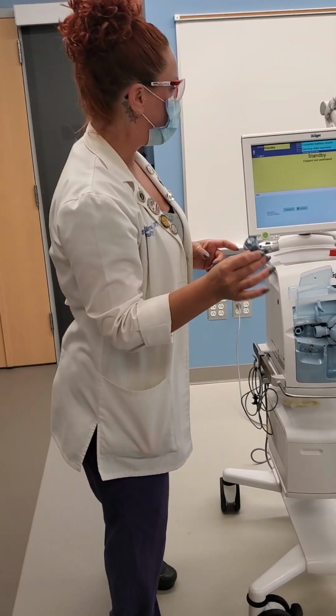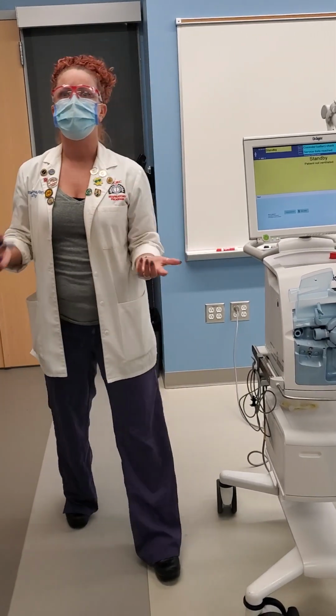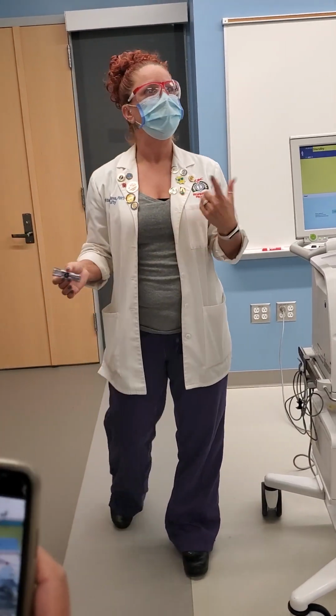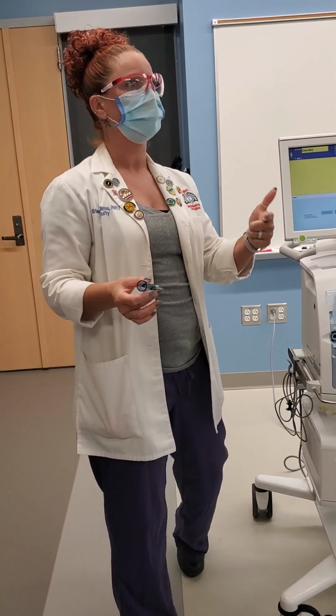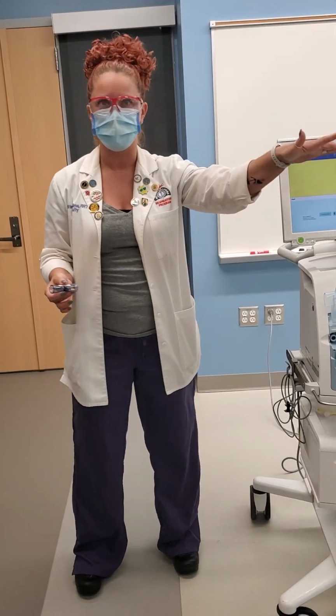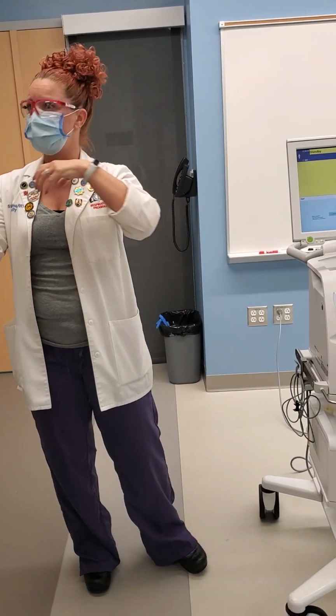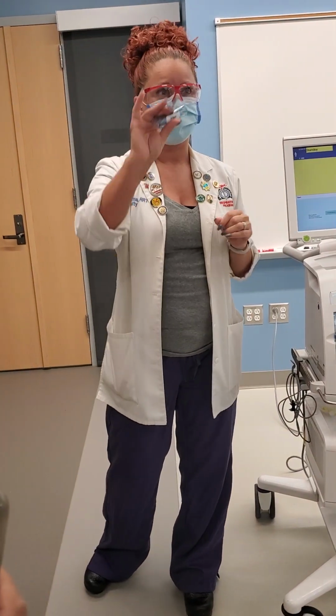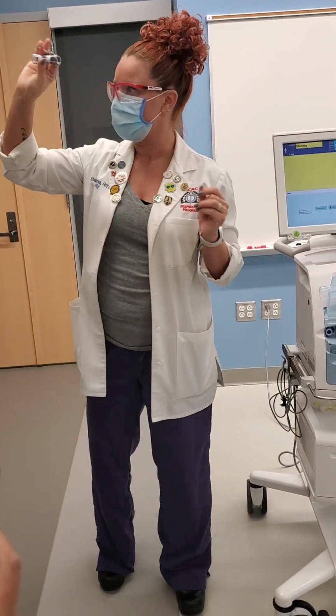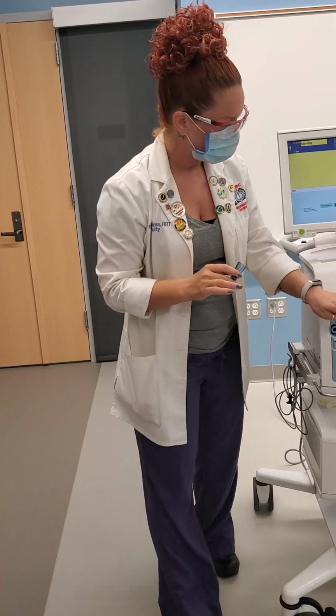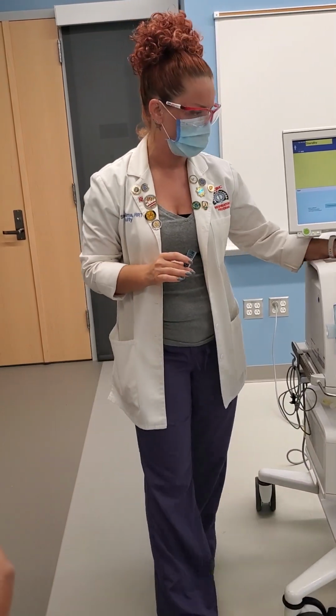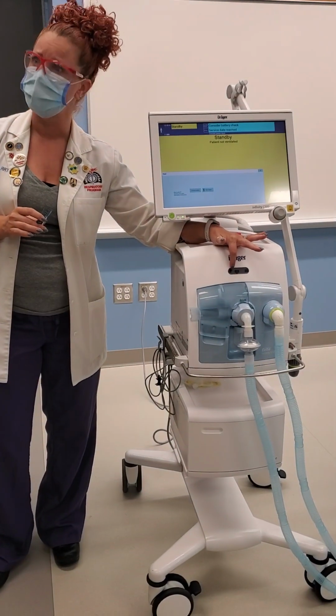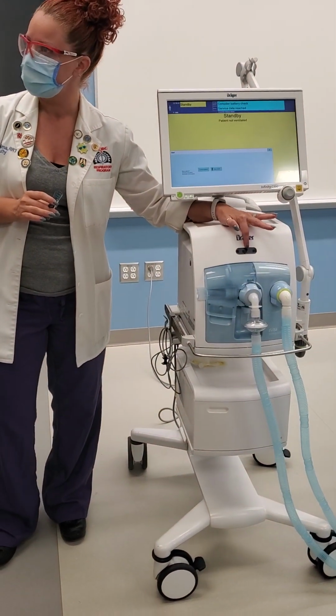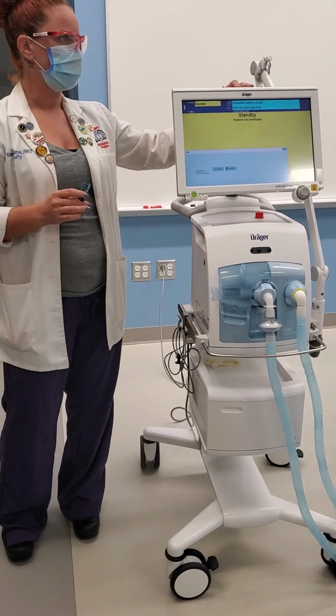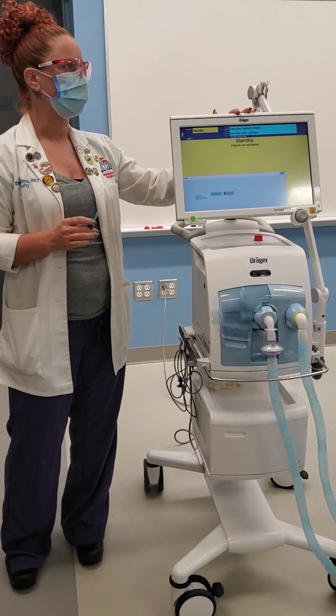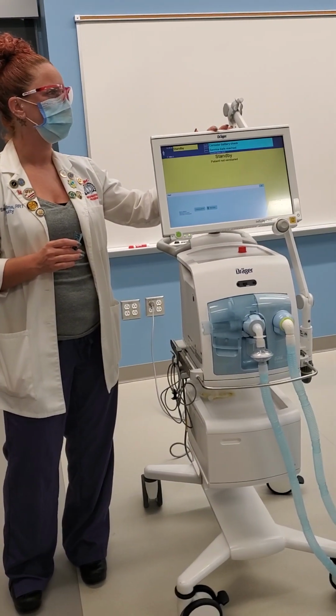So if you ever have a situation where your waveforms and your values essentially disappear, pressure will still be there, but volume and flow and your exhaled tidal volume, minute ventilation, those values will just disappear. It's the flow sensor. I can tell you that right now. You can verify that the patient is being ventilated because the minute ventilation and the FiO2 will pop up here. This is the GUI, the graphical user interface. What does the G stand for?